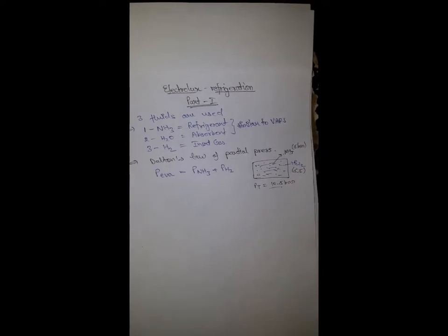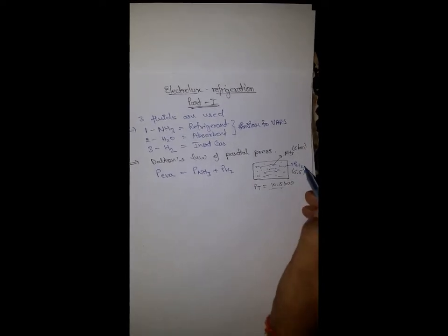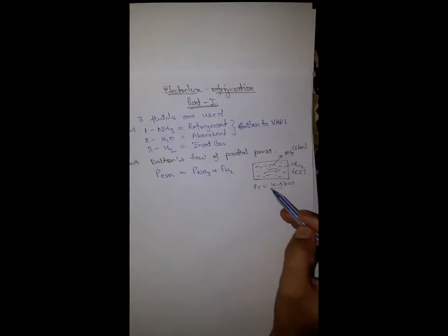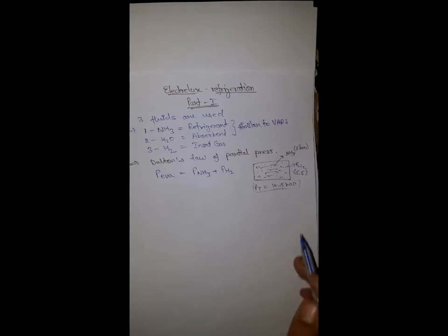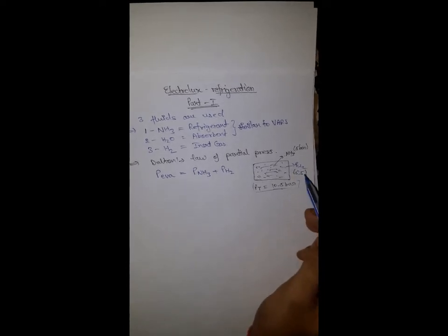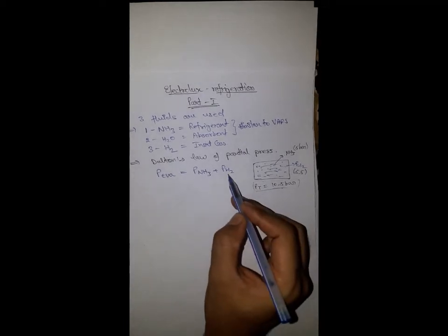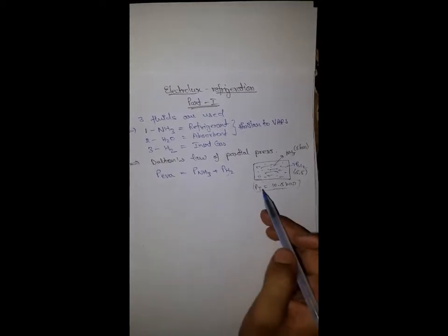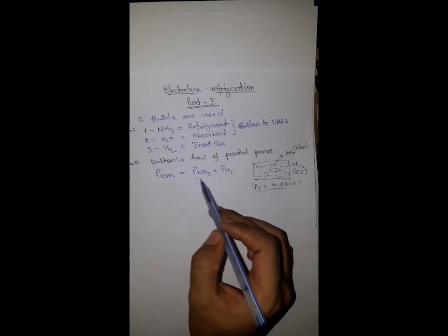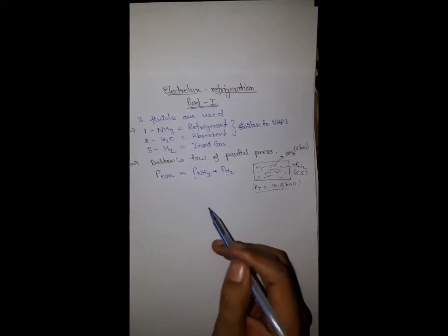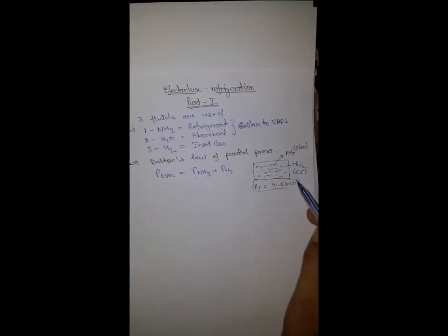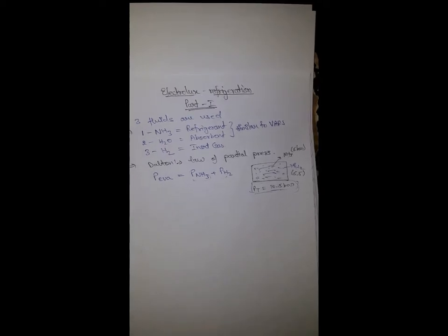If we increase the pressure of hydrogen in this evaporator, the ammonia pressure would reduce to keep the total pressure constant. This is the application of using hydrogen here. We use hydrogen for evaporating the ammonia at a lower pressure, while the total evaporator pressure remains constant.